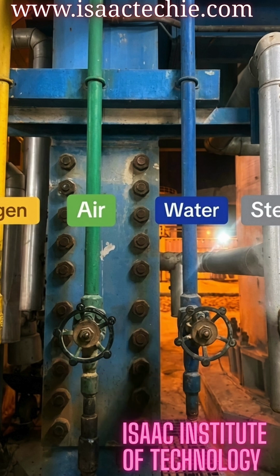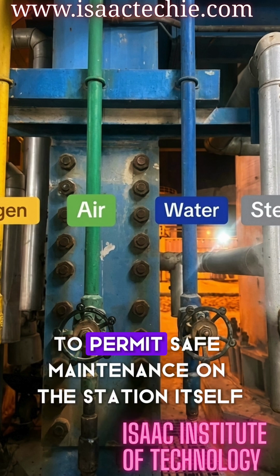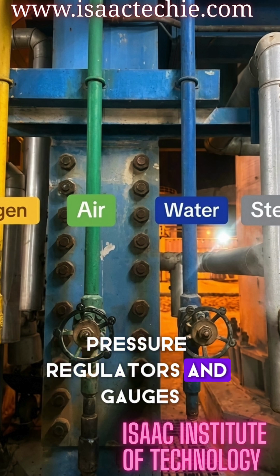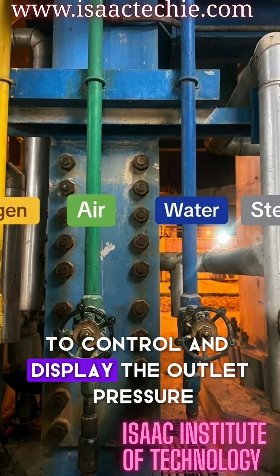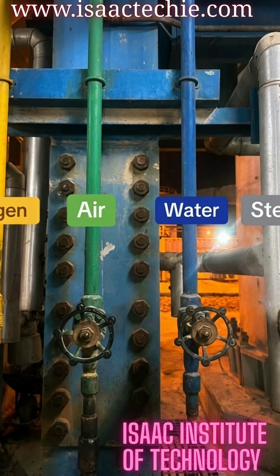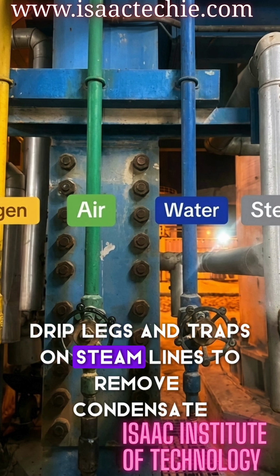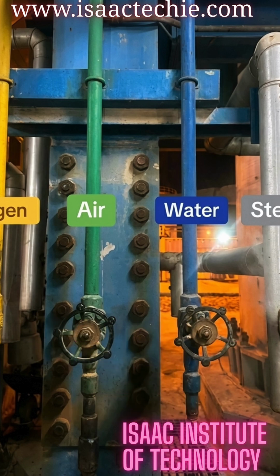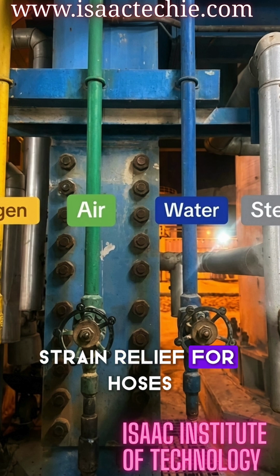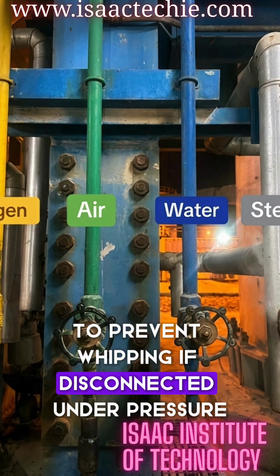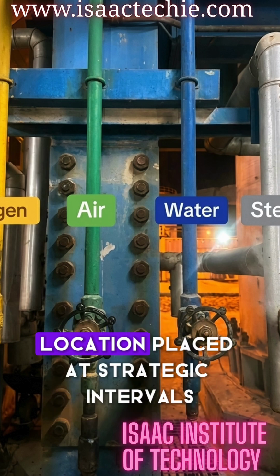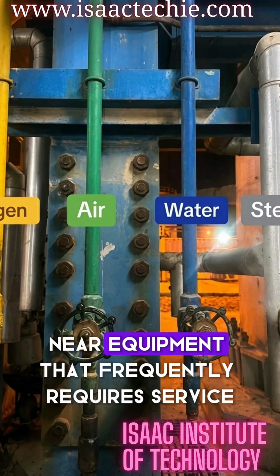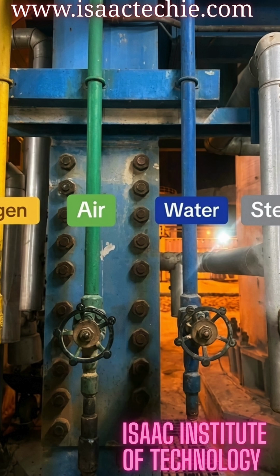Lockout/tagout points. Valves allow for isolation to permit safe maintenance on the station itself. Pressure regulators and gauges, to control and display the outlet pressure. Drip legs and traps, on steam lines to remove condensate. Strain relief, for hoses to prevent whipping if disconnected under pressure. Location, placed at strategic intervals along process units, near equipment that frequently requires service, and along escape routes.